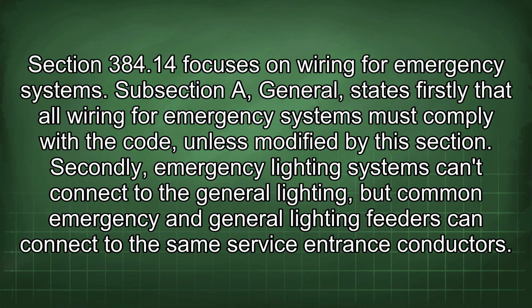Section 384.14 focuses on wiring for emergency systems. Subsection A, General, states firstly that all wiring for emergency systems must comply with the code, unless modified by this section. Secondly, emergency lighting systems can't connect to the general lighting, but common emergency and general lighting feeders can connect to the same service entrance conductors.